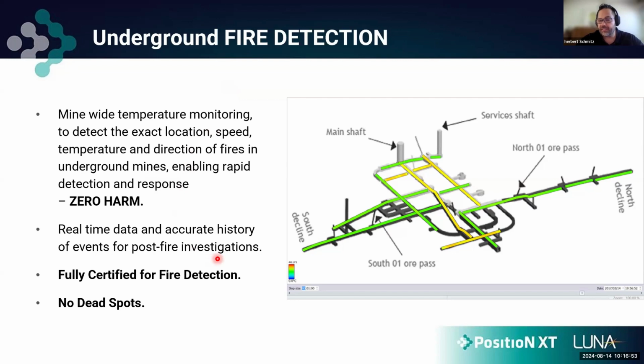All this data is saved in the database software, so we can do post-incident investigation. We can see exactly where the fire started, the temperatures, the movement of the gases along the fiber optic cable, and the thermal energies. And as I said, compared to traditional ways of thinking, no dead spot. Wherever the fiber optic cable is running, we are monitoring.